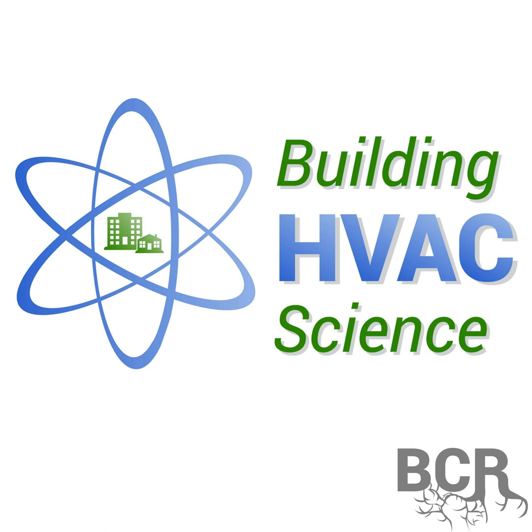But yeah, we will have to see how long it takes before filters do get changed. One of the nice side benefits of larger filters is that they take a lot longer to get loaded up. So I've done some testing about that at my house, going as long as 10 months in between filter changes on a 3/4 ton heat pump that pretty much just the air handler runs at various speeds, but it runs just about 24/7 all year round.